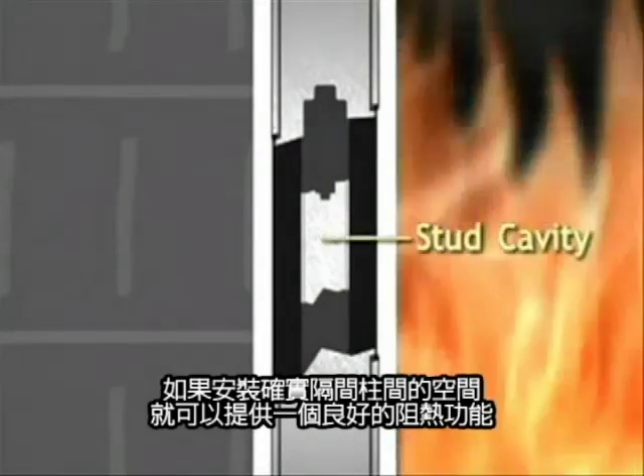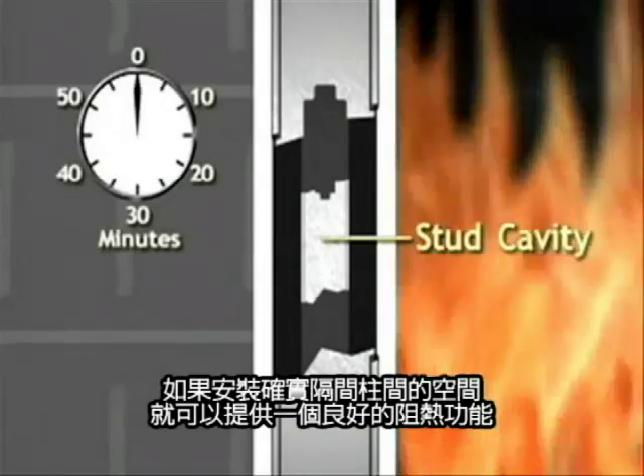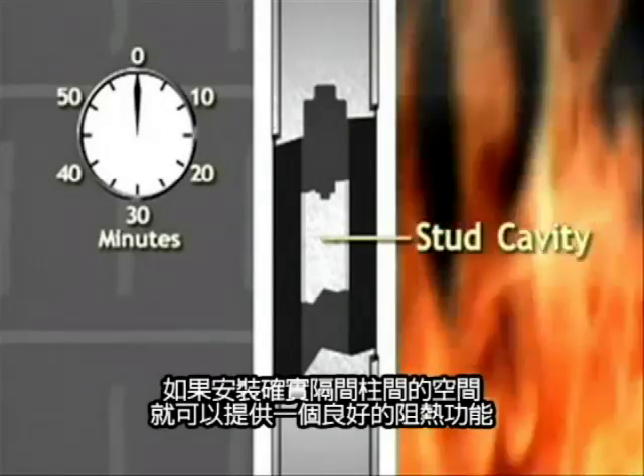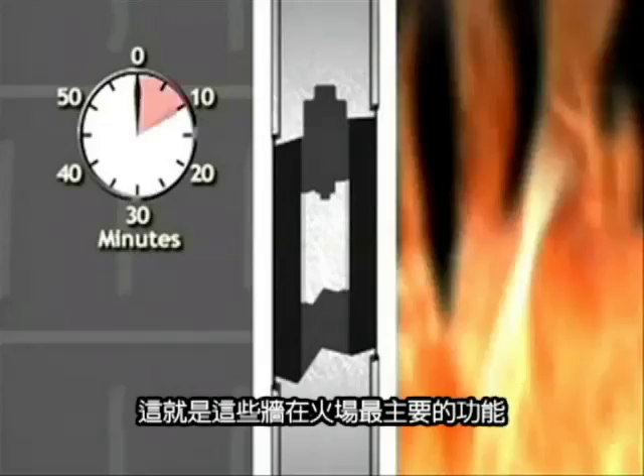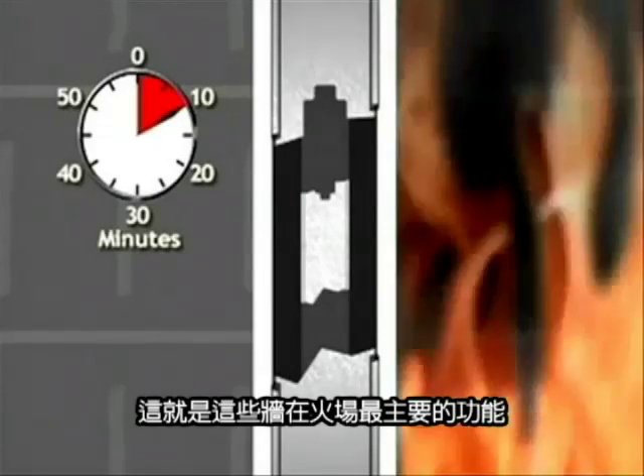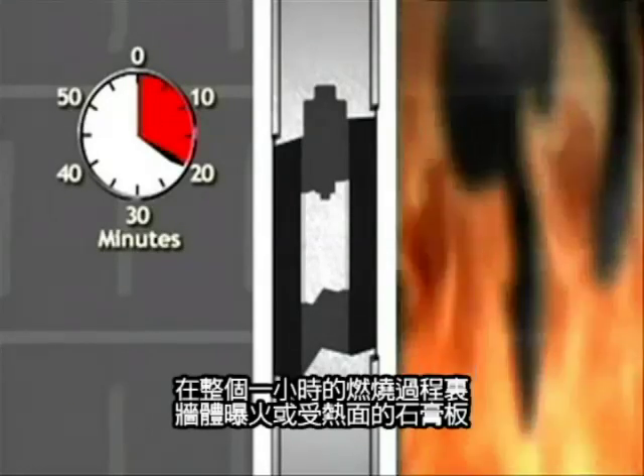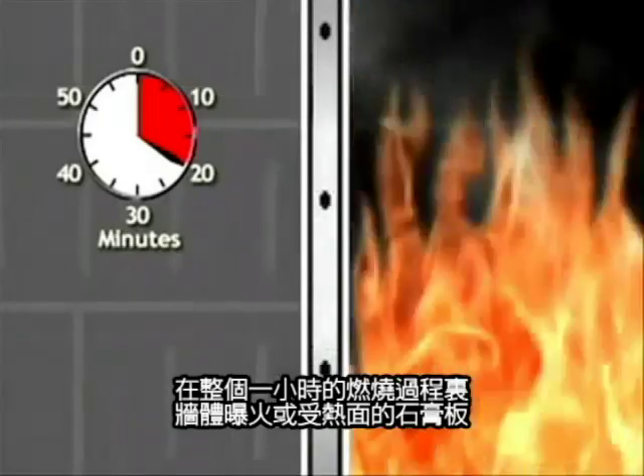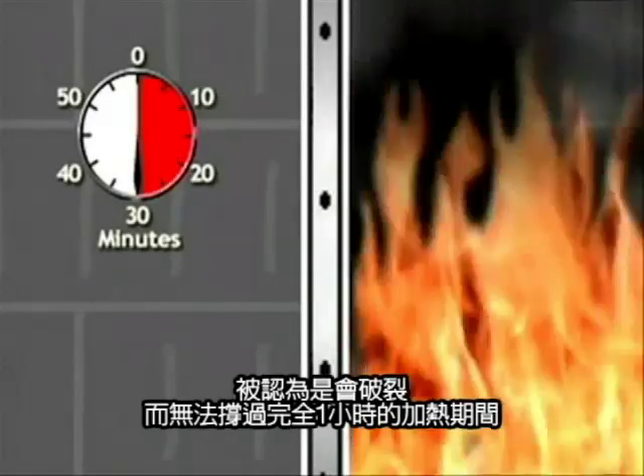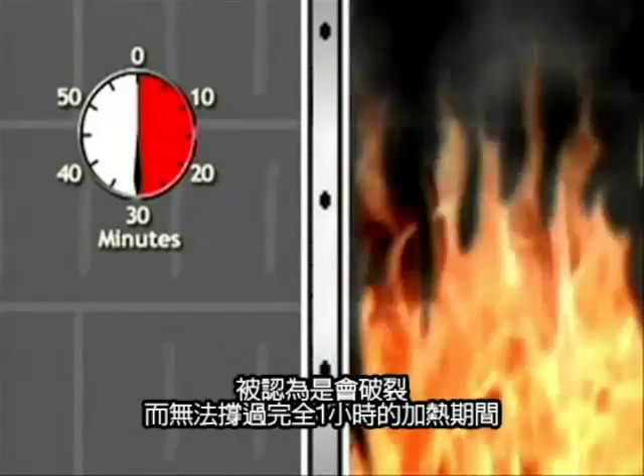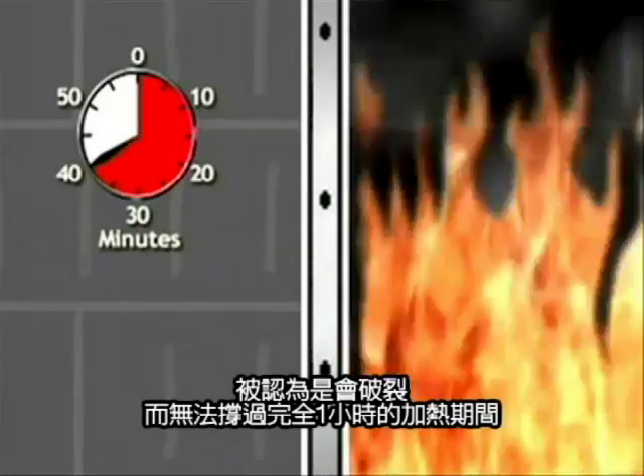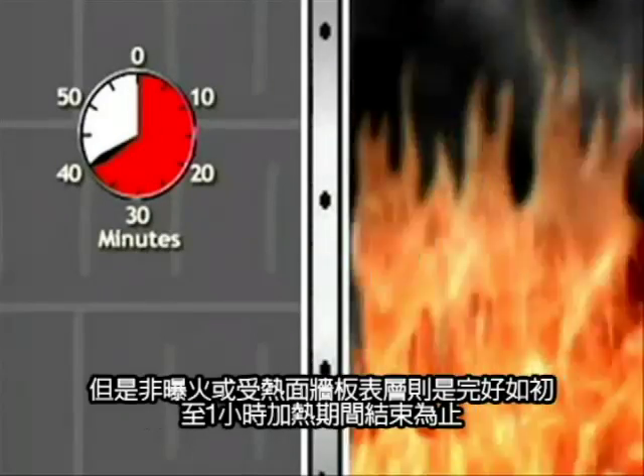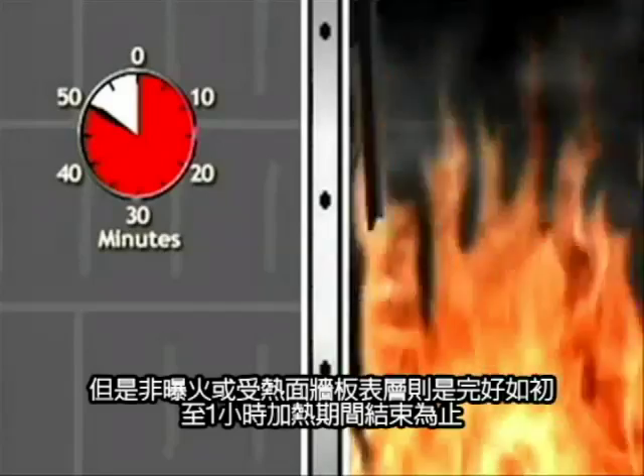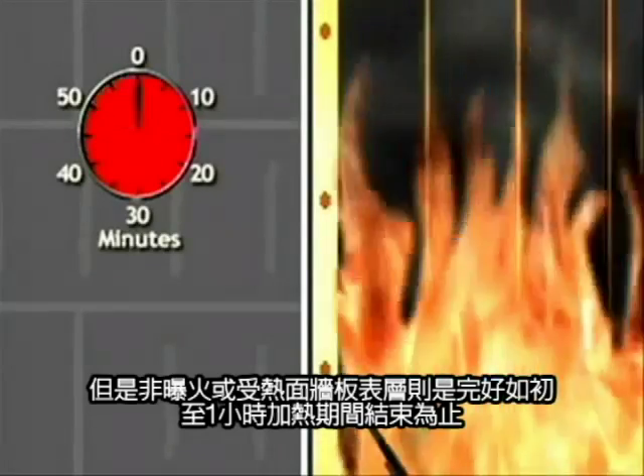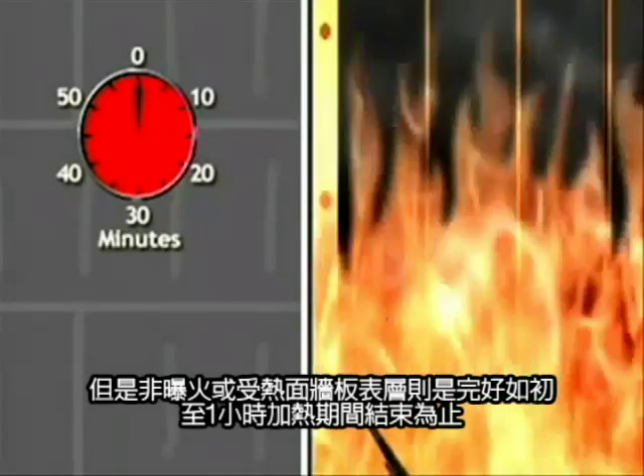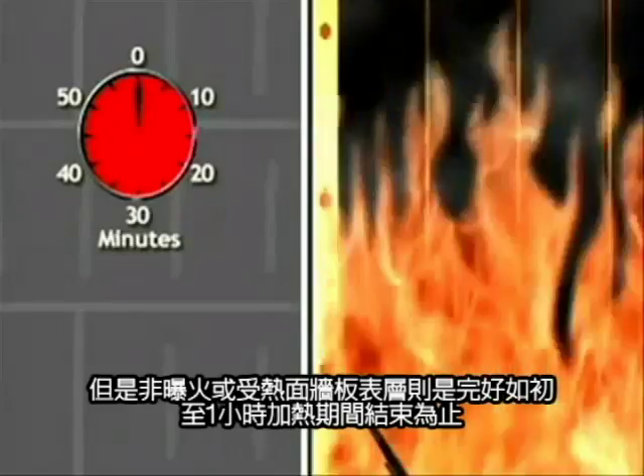When erected properly, the stud cavity becomes an airspace that provides excellent thermal insulation, which is a key to the performance of these walls in a fire. The layer of gypsum board on the exposed or hot side of the wall is considered sacrificial and is not expected to survive the full hourly duration of a fire, provided that the last layer of the wallboard on the unexposed or cold side is fully intact at the end of the hourly duration.